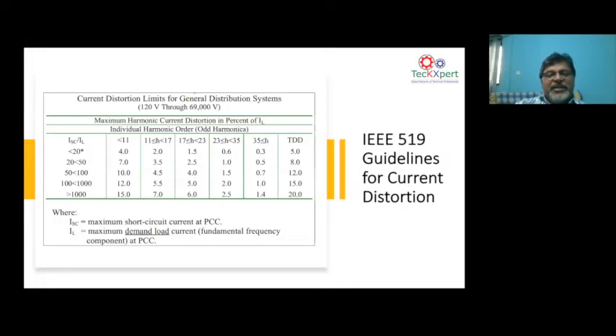Go to the next. Here it talks in terms of current harmonics. The current harmonics limit goes by the fault level of the network. But again, in the IEEE, we go by the TDD, not the THD, because THD is an instantaneous value. TDD is computed based on the full load current. THD is calculated based on the instantaneous fundamental current. So if you want to implement a harmonic study according to IEEE norms, you need to look at these tables and very carefully make sure that it complies in terms of TDD. You don't have to worry about THD. You have to look into TDD.